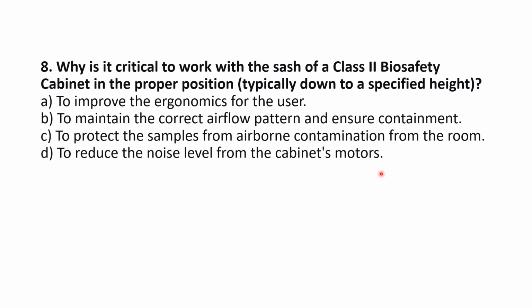Now the correct answer here is to maintain the correct airflow pattern and ensure containment. B, without question, because the regulations are that we need to always work with the cabinet sash down to maintain containment. This is a class 2 biosafety cabinet. The sash height is calibrated to ensure the inward airflow, or the air curtain, is sufficient to protect the user and prevent particles from escaping.